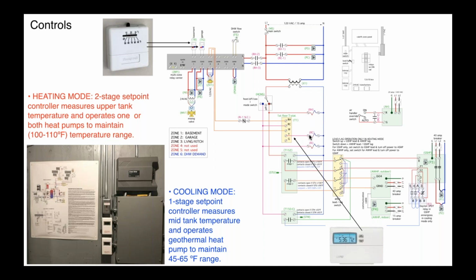So we use the relays basically to integrate more specific logic to the system. And by the way, the relays that I've used for years, they're Dayton relays. They are triple pole double throw. And oftentimes we don't need to use all 3 poles on the relay, but I'm going to share a story with you in a minute here. It's always nice to have extra switching capability in relays. You may want to modify the system down the road. You may want to turn something else on. And literally for a couple dollars more, you're buying a triple pole double throw relay as opposed to, let's say, a single pole single throw relay.